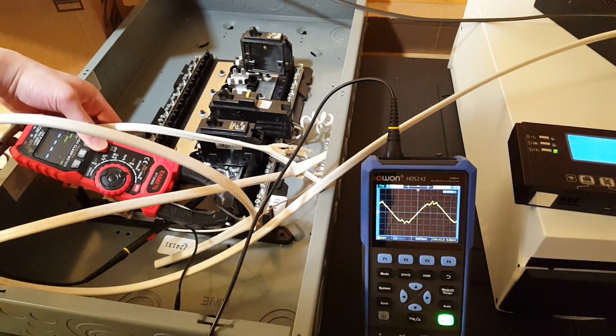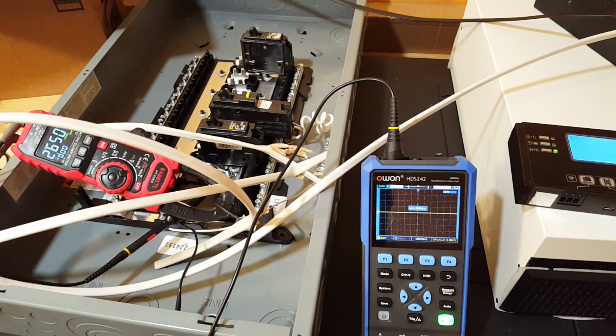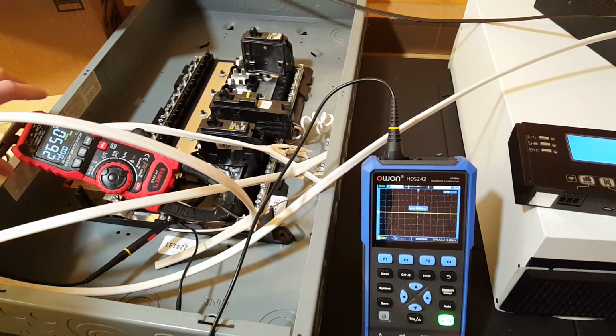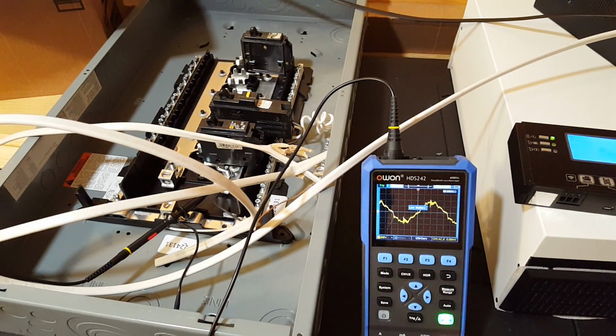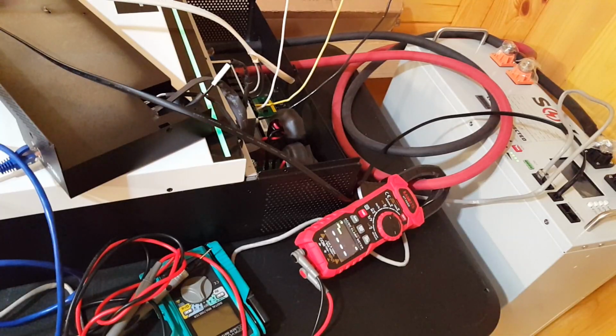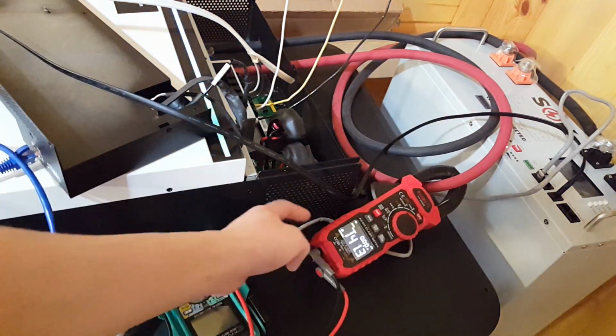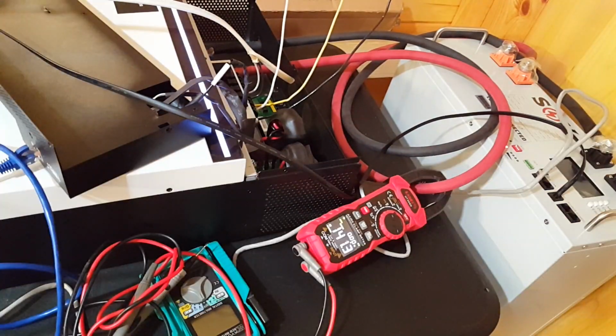Let's try it a few more times. Attempt number 2. It said 59.2 amps inrush. It failed this time, the DC surge. Let's measure that. Battery's back online. Will it try it the third time? Nope. 141 amps on the DC surge. 141. That's a difficult one to start.